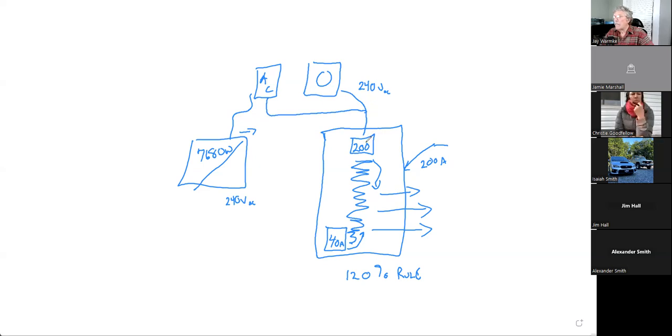So it's got to be between your main and the meter. If I hook up on the other side of the meter, then I'm just feeding the grid and I'm not getting any credit for it. So I wouldn't bother with that. But a supply side connection, you're going to connect in here.